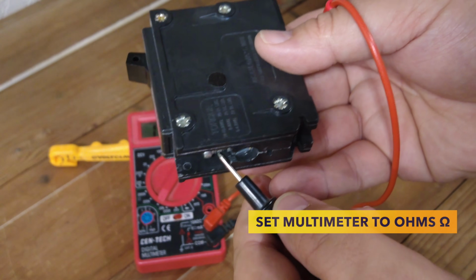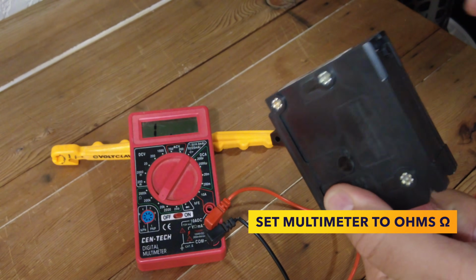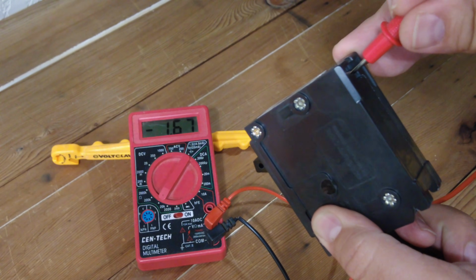Now, as a final check, if you want to test a breaker to see if it's bad or not, and you have the breaker removed from the panel, you can use a basic multimeter to do a test to see if the breaker is bad or if it's something else. So again, if you have the breaker out of the panel and it won't stay in the on position, then that's a good indication that there's a mechanical failure inside of this. If it will stay in the on position, you can take a multimeter and put it to the terminal screw on this, and then also on the connection clip in the back, and see what reading you get.